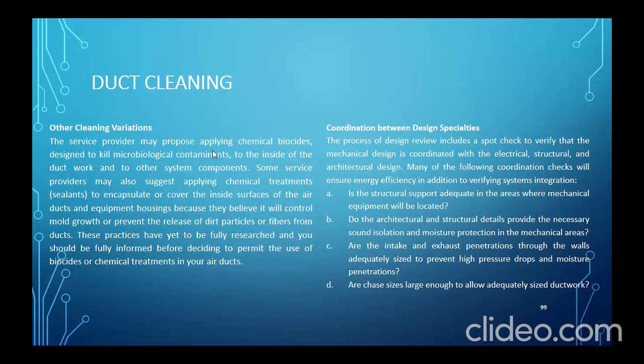Other cleaning variations. The service provider may propose applying chemical biocides designed to kill microbiological contaminants to the inside of the ductwork and to other system components. Some service providers may also suggest applying chemical treatments, sealants, to encapsulate or cover the inside surfaces of the air ducts and equipment housing because they believe it will control mold growth or prevent the release of dirt particles or fibers from the duct. These practices have yet to be fully researched, and you should be fully informed before deciding to permit the use of biocides or chemical treatment in your air duct.